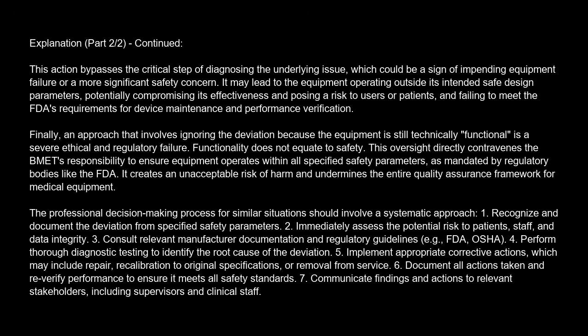Finally, an approach that involves ignoring the deviation because the equipment is still technically functional is a severe ethical and regulatory failure. Functionality does not equate to safety. This oversight directly contravenes the BMET responsibility to ensure equipment operates within all specified safety parameters, as mandated by regulatory bodies like the FDA. It creates an unacceptable risk of harm and undermines the entire quality assurance framework for medical equipment. Professional decision-making process for similar situations should involve a systematic approach.